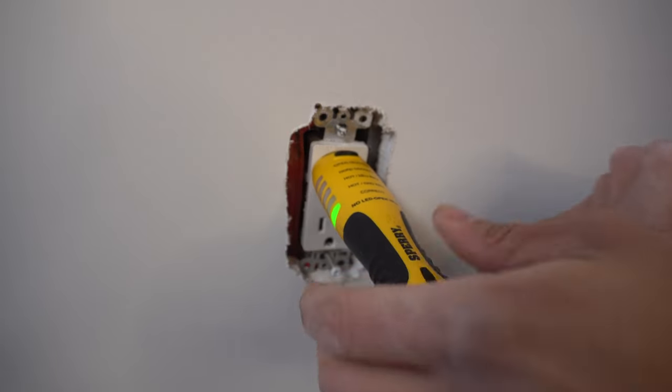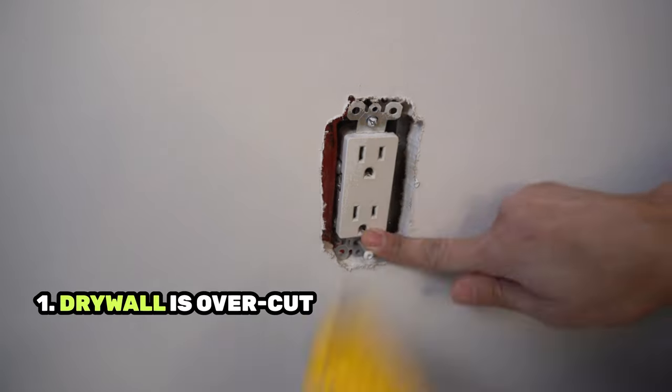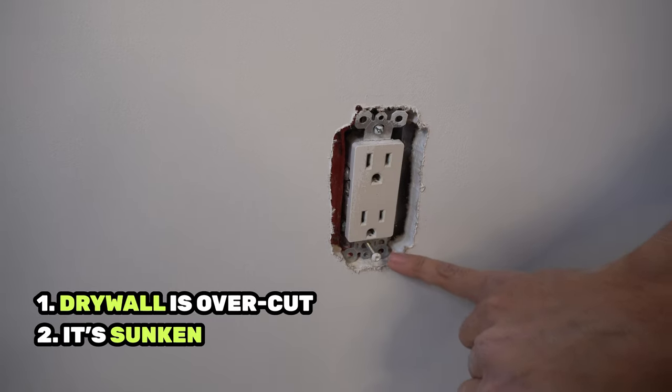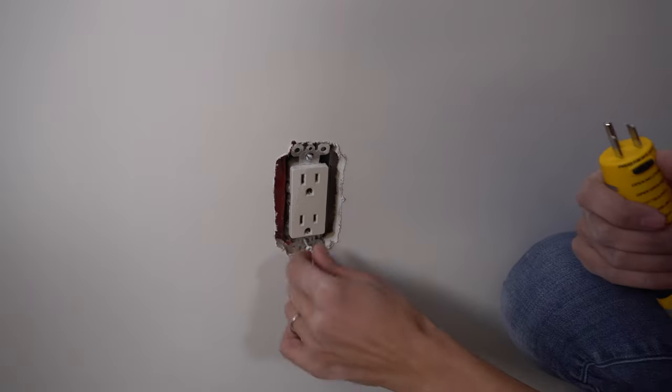So we can see that this is wired correctly, but it is actually overcut, meaning the drywall is cut way too far and it's sunken, meaning the box is recessed in behind the drywall. That is absolutely illegal.